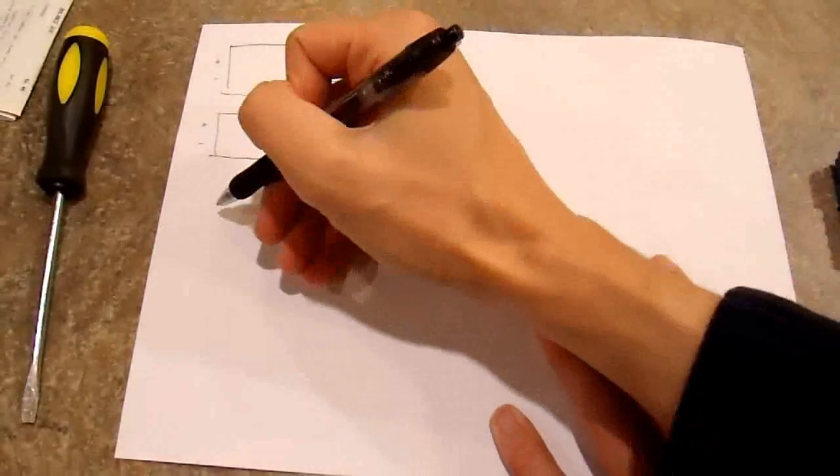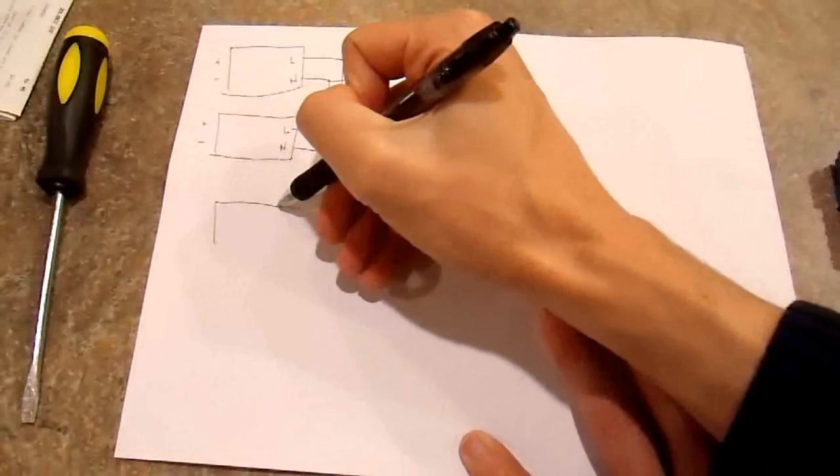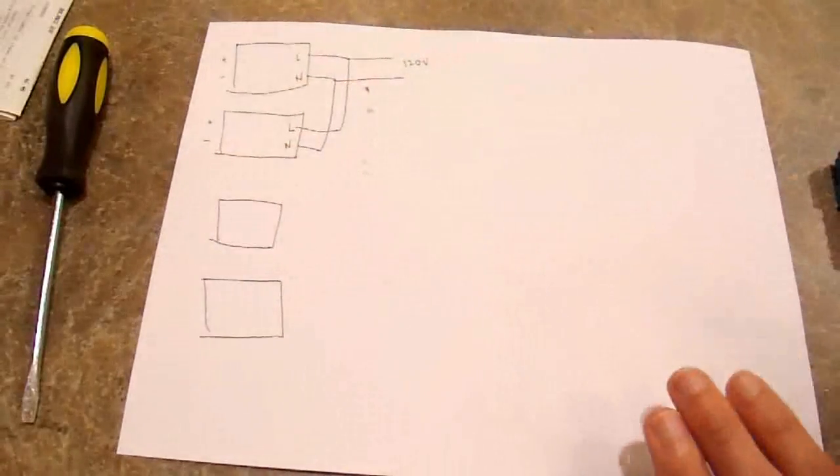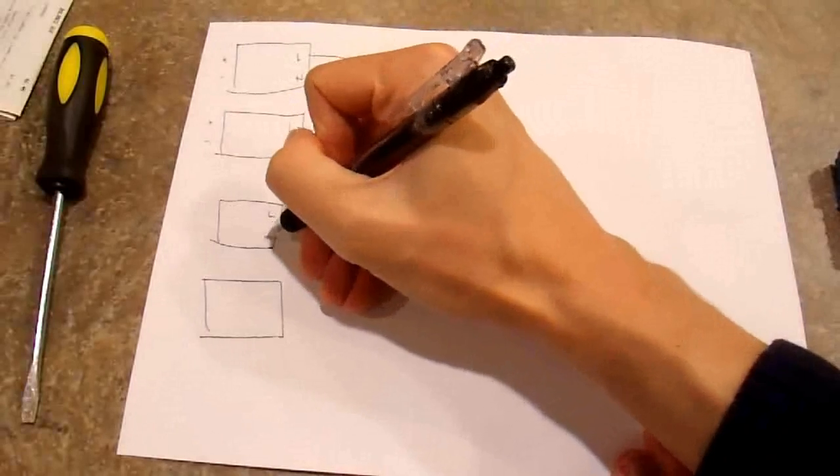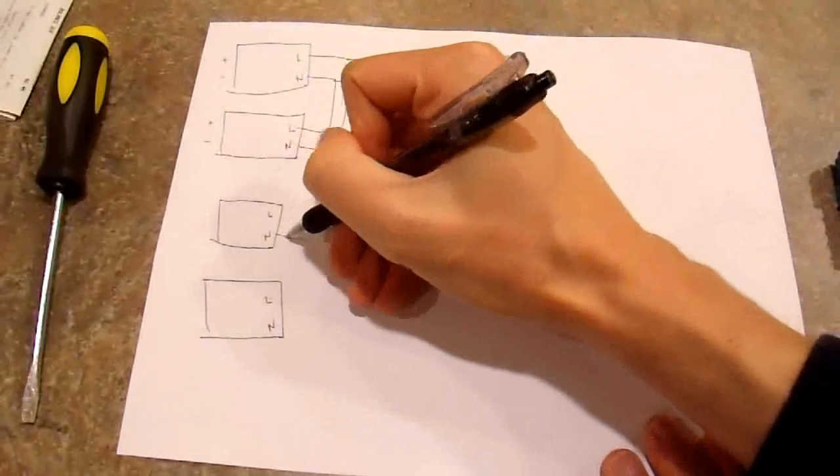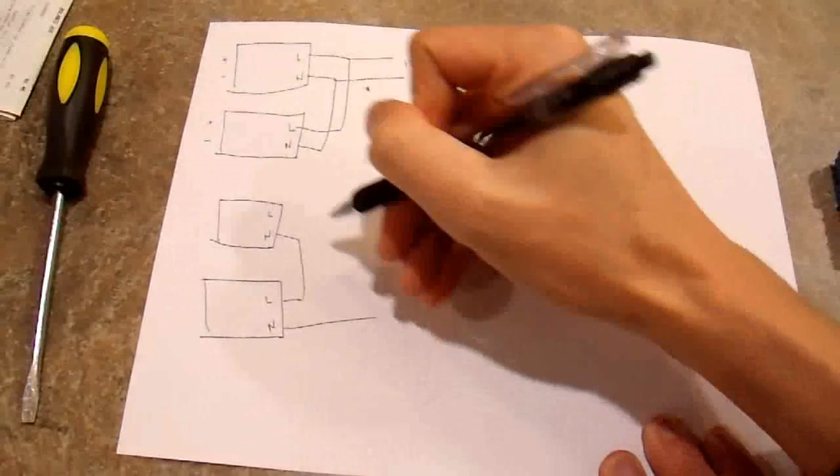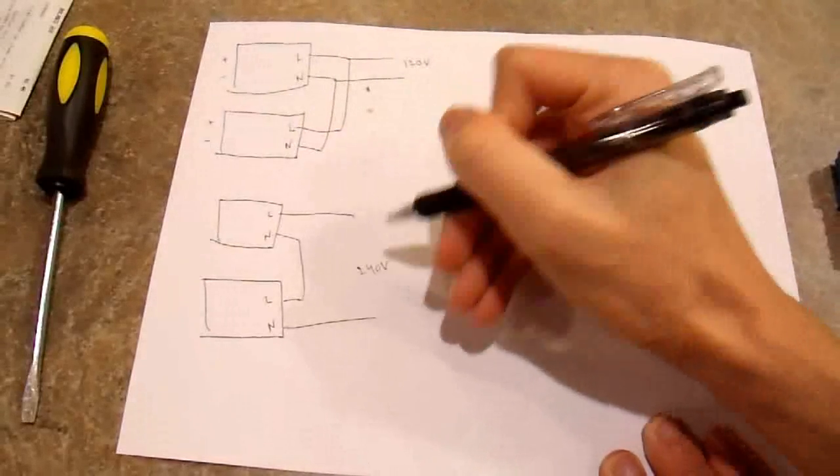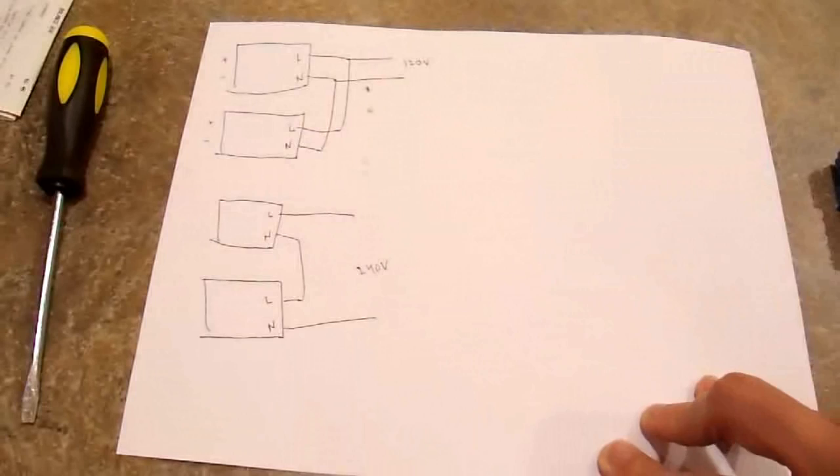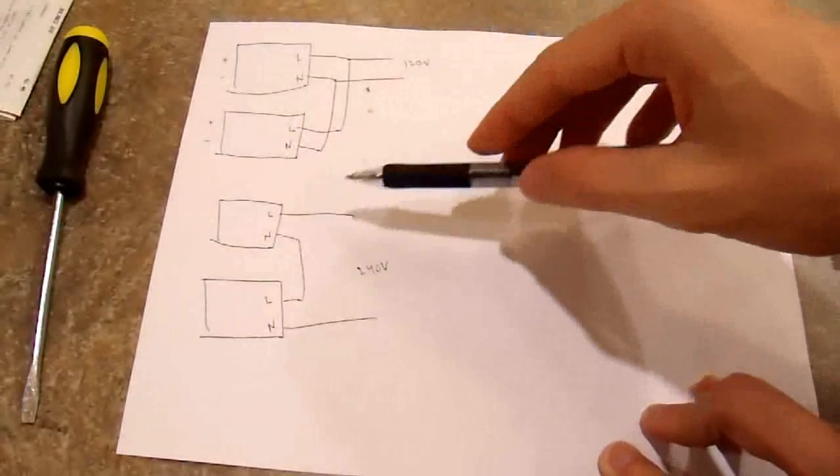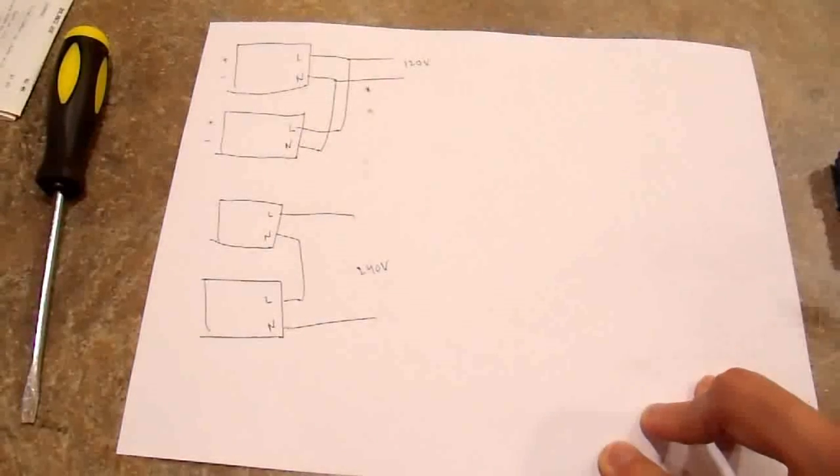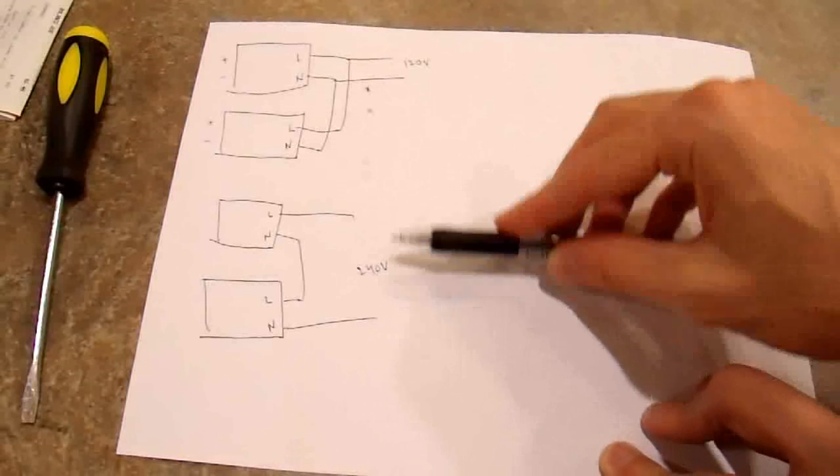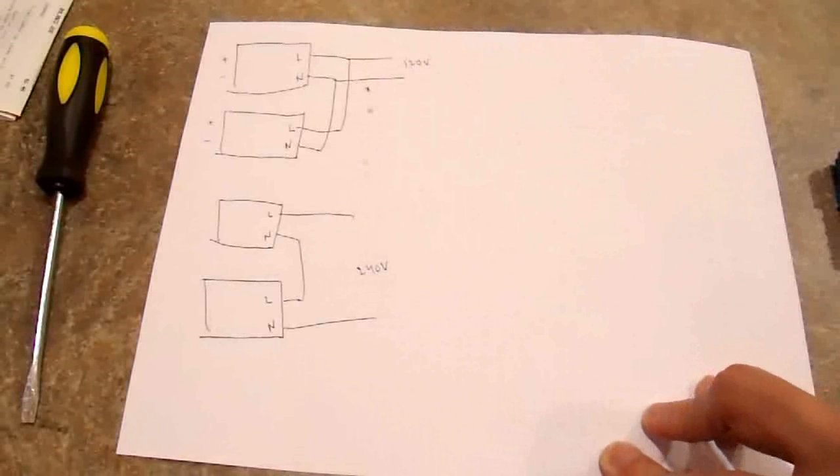The other topology is series, which is basically the same thing. Line neutral, line neutral. But in this case you connect neutral and line together and send this out. And if you're running on a 120-volt system, this would be 240 volts. You would only have half the current but double the voltage. So you'd still get 3000 watts out at 240 volts, or 3000 watts out at 120 volts this way.